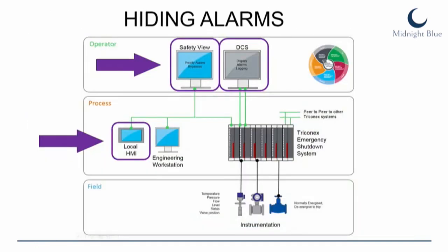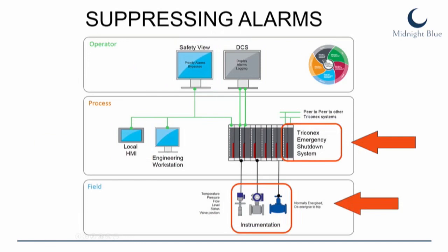So how do we go about this? We can hide the alarms by compromising the safety view, the DCS view, or some local HMIs. This is the benefit of hiding them centrally, but still these alarms go out as network traffic, and we don't want any kind of network inspection to see these alarms. So we want to suppress them either at the field level, the level of the field devices, or at the level of the safety controller itself, which is what TriConex is.